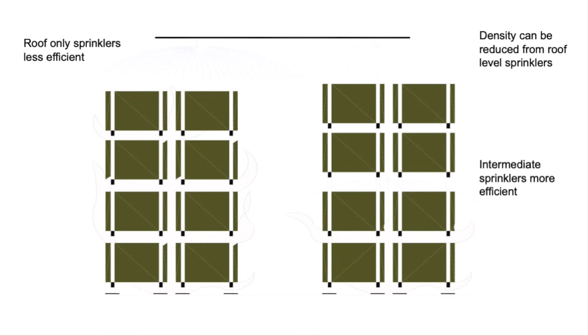in-rack protection. When you've got in-rack protection, the head's placed in the middle of the racks. The middle of the racks we call the flue. That's the longitudinal flue, which runs the full length of the rack. That has to be kept at a minimum of 150. And that allows the water to flow down and through and make sure that we're catching all the areas of potential fire spread. Okay.